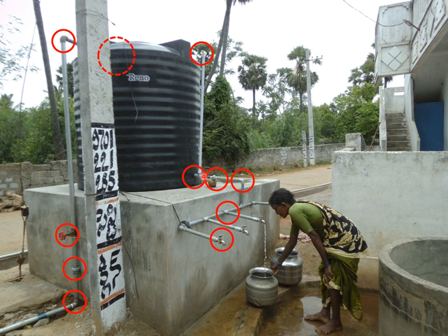We can see there is a union connected here — we will discuss the purpose of union in coming slides. Then there is an elbow again. The pipeline is directed downwards and this is the branching. There is a T installed, an elbow installed, another T installed, another elbow installed, and these are all pipes. In this case, this seems to be a 15 mm pipe only, whereas the supply line seems a bit thicker and may be of 25 mm.